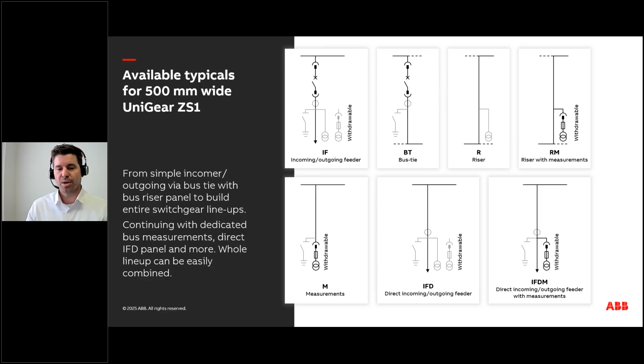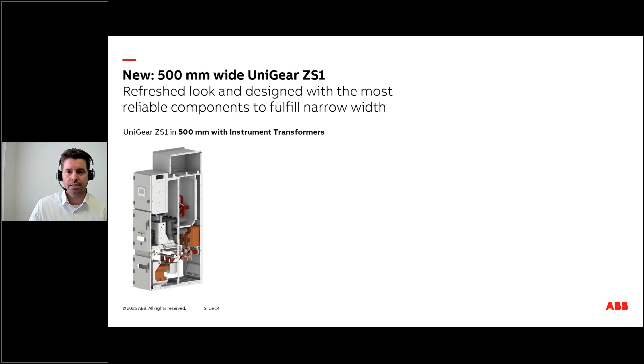Now let's look into the panel itself. The 500 mm comes with a refreshed look and is designed with the most reliable components. From the design perspective, the panel is available in two variants. First comes with instrument transformers, and the second variant is available with low power instrument transformers. The key component is the famous VD4 type circuit breaker, used also here with embedded poles. The second key component is the thermoplastic spouts, which help to improve the recyclability level. Third is the earthing switch from our EK family. The latest evolution of the earthing switches is the EK7 type.